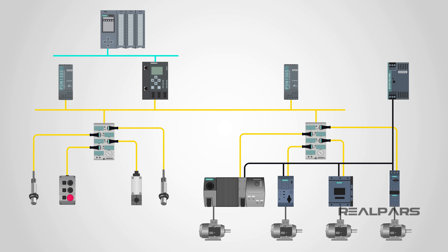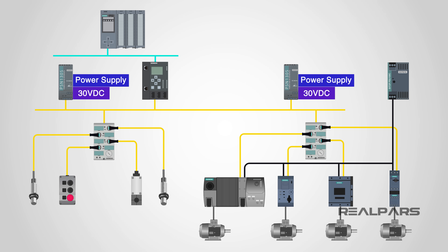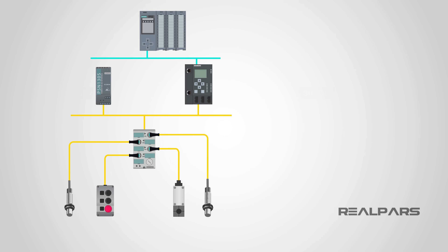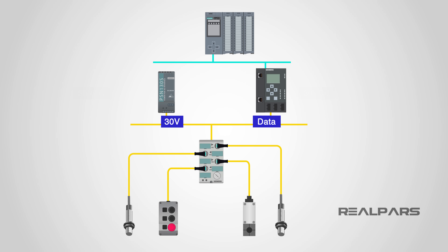Finally, we have a power supply unit. The unit provides a constant regulated 30 volts DC to supply power to the master and the slave devices. It also works as a data decoupler, which means it separates the power and data, as they are both simultaneously transferred along the cable.